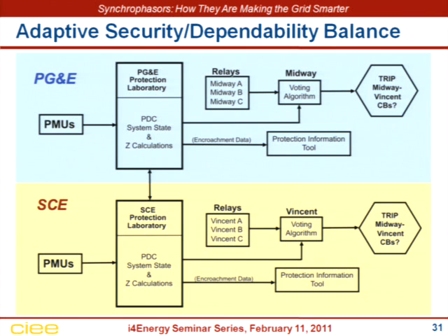The information goes out to what's called a voting algorithm. On this transmission line, as is similar for a lot of 500 kV high voltage lines that are very critical tie lines between companies, we have redundant relaying systems. There's actually three of them. So this is not just belt and suspenders, it's also safety pins holding your pants to your shirt. Because if your belt fails, your suspenders hold them up, and if that fails, then safety pins are the last. Anyway.